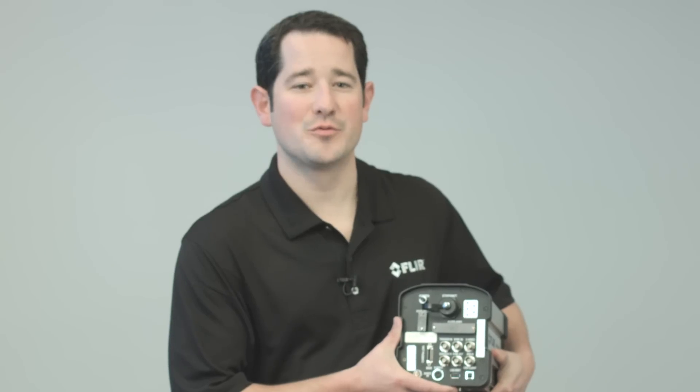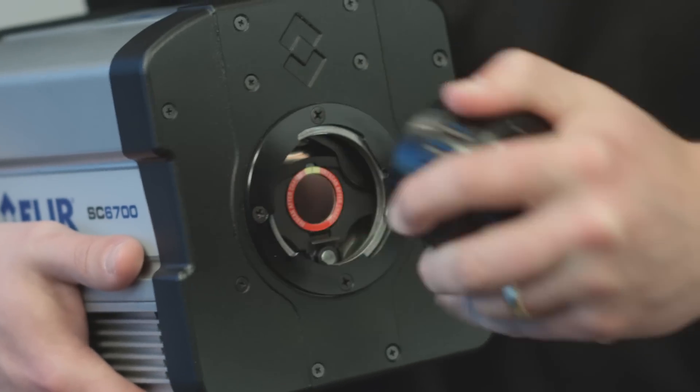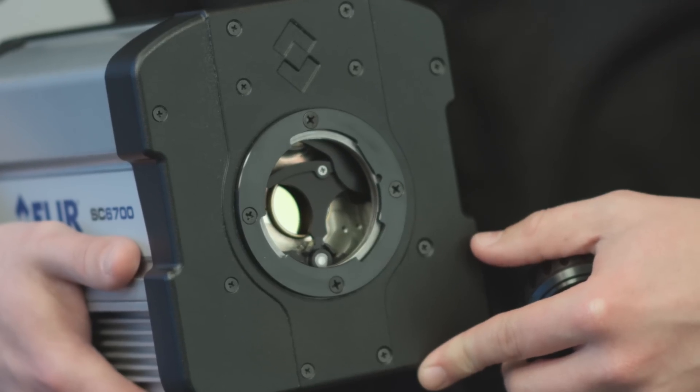This provides a true deterministic time-stamp of every frame for easy and accurate correlation to other devices. Last, the SC6700 has a four-position filter wheel that uses a binary coding system tied to the command and control GUI. Therefore, spectral or neutral density filters are recognized and can be controlled remotely via a drop-down menu.